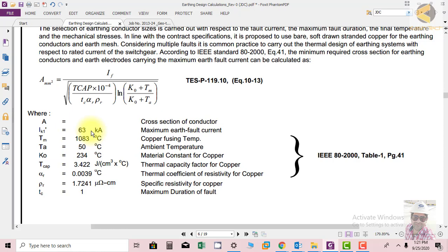and submit a complete system, then you can calculate it or it might be provided by the utility. But the thing is, fault level of substation does not remain the same all the time. I will give you an example: a substation with four transmission lines connected from power plants. If only one line is feeding the substation the fault level will be low, and if more sources are added the fault level will increase accordingly.